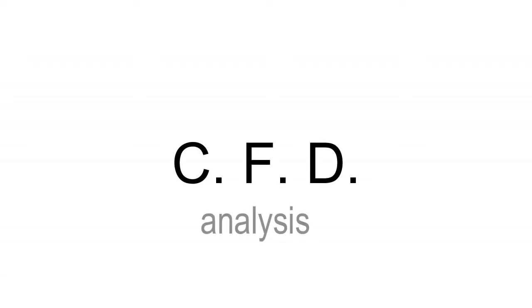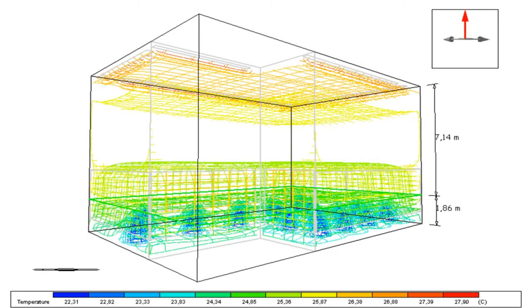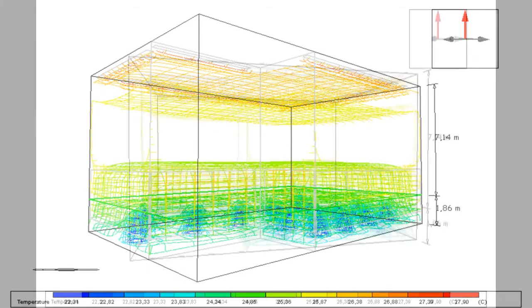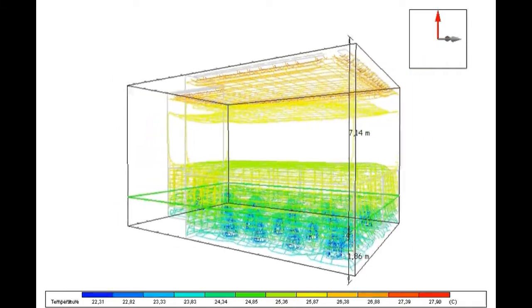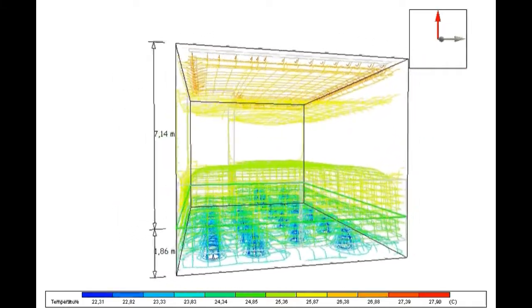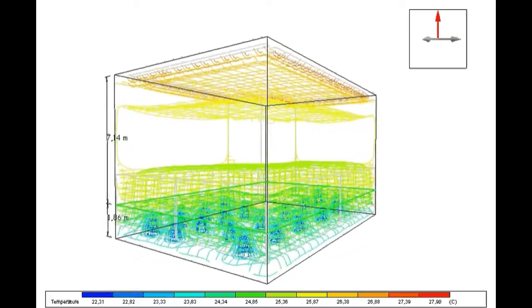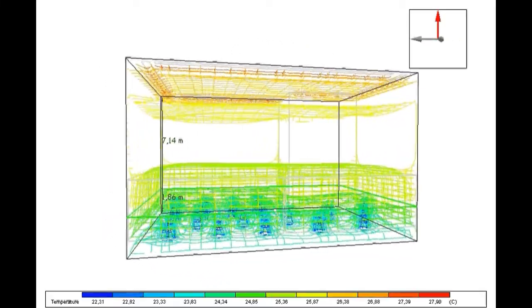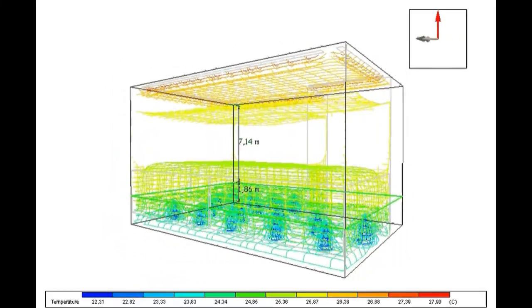Conducting the CFD analysis in Design Builder software for the cooling operation, we took the atrium and a common small office to show the streamlines and the temperature zones formed by the underfloor air distribution system, implemented in our building. Because of its height of 9 meters, 30 feet, the atrium is considered a large space. The air outlet diffusers are mounted into the first floor ceiling because of the atrium's interior layout. Detailed analysis in the atrium show that the calculated flow of 0.648 cubic meters per second was not sufficient to maintain the required thermal conditions in the room.